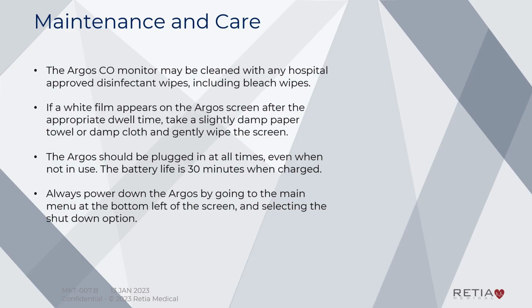In regards to maintenance and care, the Argos cardiac output monitor may be cleaned with any hospital-approved disinfectant wipes, including bleach wipes. If a white film appears on the Argos screen after the appropriate dwell time, take a slightly damp paper towel or cloth and gently wipe the screen. The Argos should be plugged in at all times, even when not in use. The battery life is 30 minutes when charged. Always power down the Argos by going to the main menu at the bottom left of the screen and selecting the shutdown option.